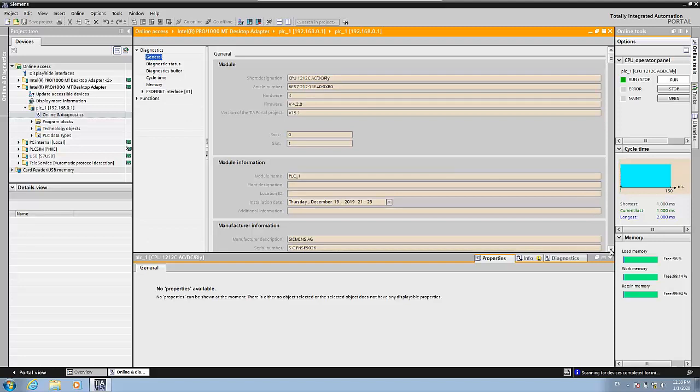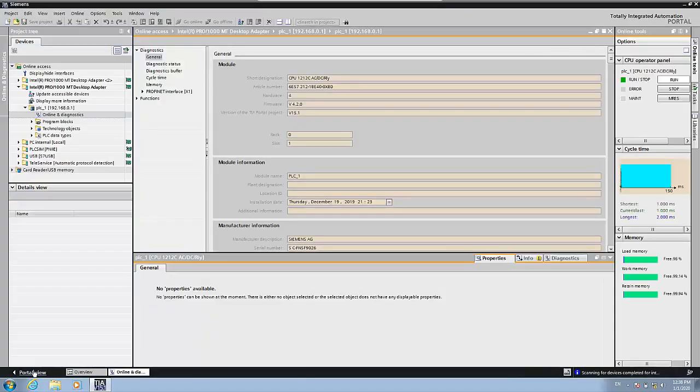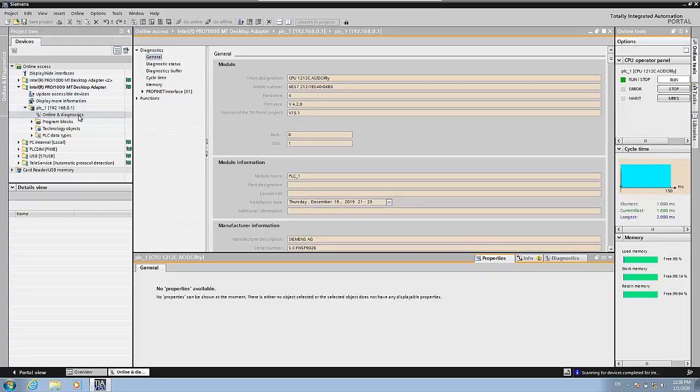So let's remember. First, the first thing that we have to do is to open TIA Portal. After that, in the portal view, you go to online diagnostics and click on accessible devices. This starts to scan the whole network. And after that, you select the PLC that you want and click on show. After you click on show, you go here to the project view to the folder of the PLC inside the network adapter in the online access folder. And double click on online and diagnostics. And here you have access to all the data of the PLC.